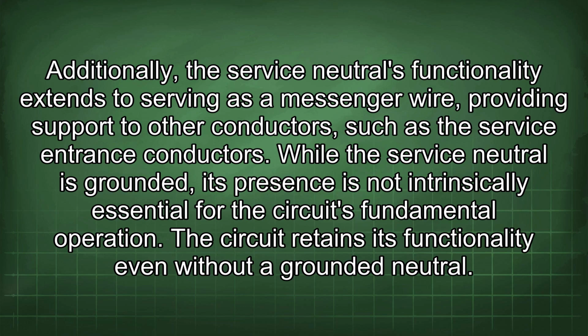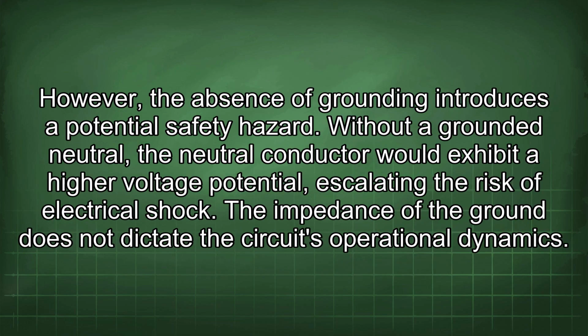The circuit retains its functionality even without a grounded neutral. However, the absence of grounding introduces a potential safety hazard. Without a grounded neutral, the neutral conductor would exhibit a higher voltage potential, escalating the risk of electrical shock. The impedance of the ground does not dictate the circuit's operational dynamics.